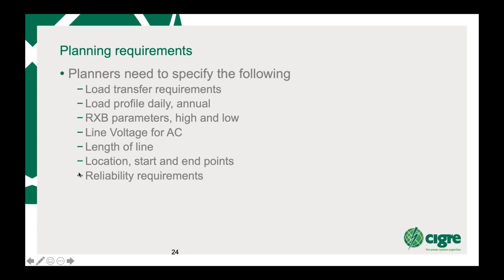And this is important to understand, that the planners need to explain the importance of this line in the network so that you know whether to design it to a level two or level three, 500 year return period, 50 year return period, or 150 year return period for the mechanical loading. So this is important, the reliability.